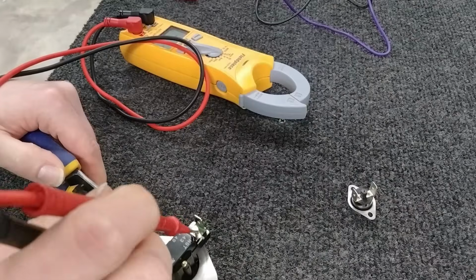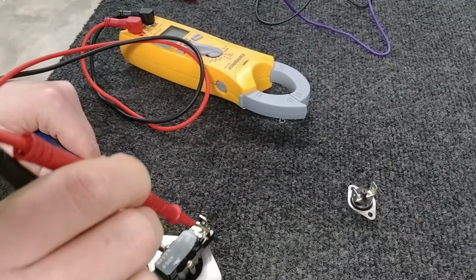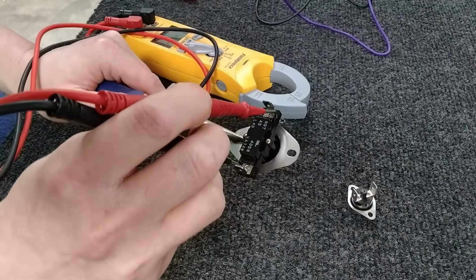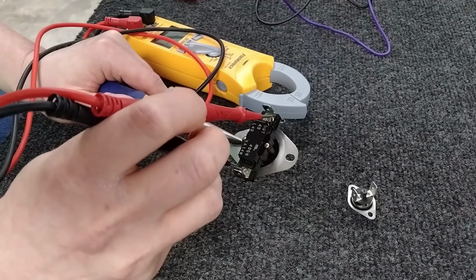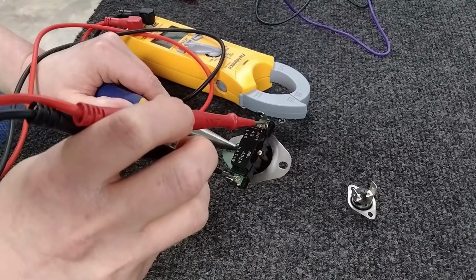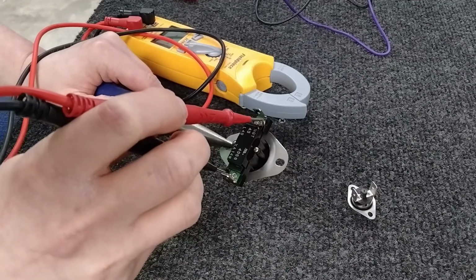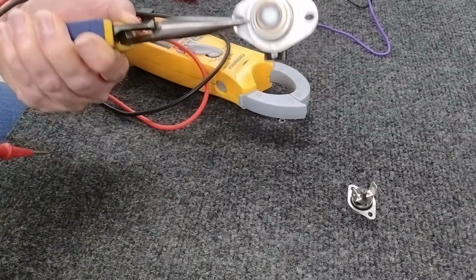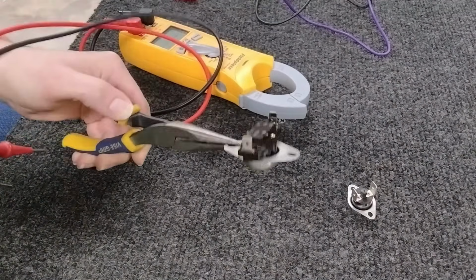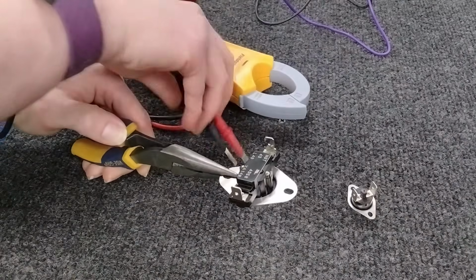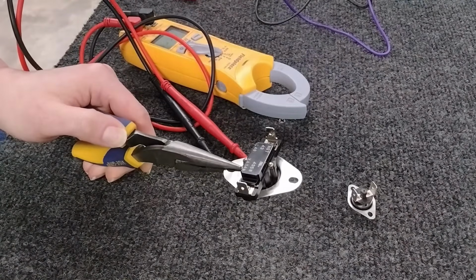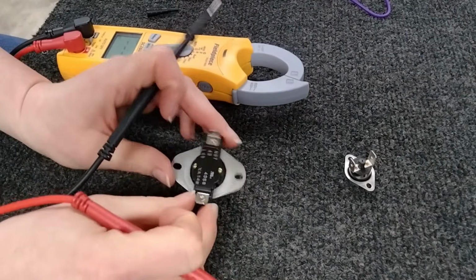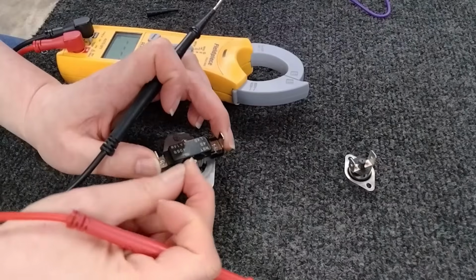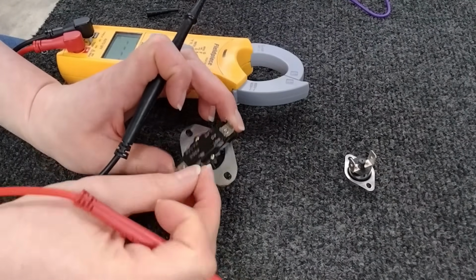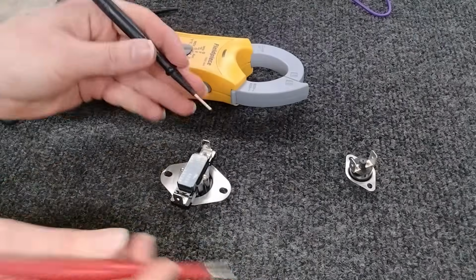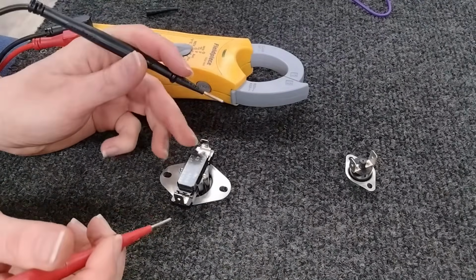Yeah, it's open. Okay, so you should not be reading continuity here when you put your leads on the metal. If you are reading continuity after you are 100% sure you've put enough fire on it, just like that, where we started to get some blue ring around there, then you know it's bad. So that's another good way of telling if it's getting stuck. After we let that cool down a little bit, you should hear the pin let go, which means the disc is going to go flat again, closing that circuit. And there you go, you've got continuity.